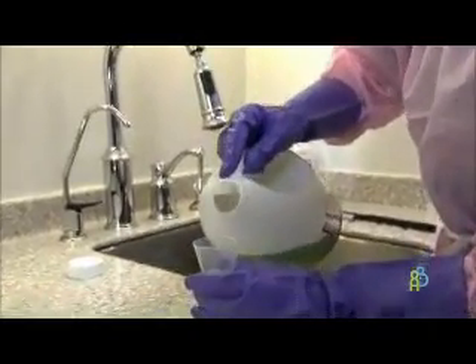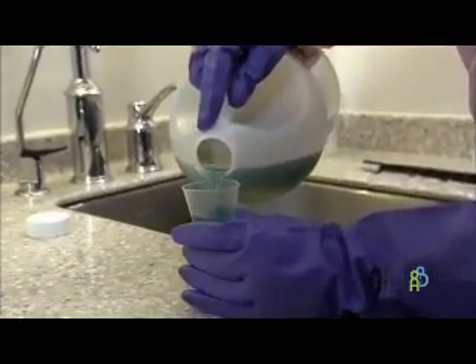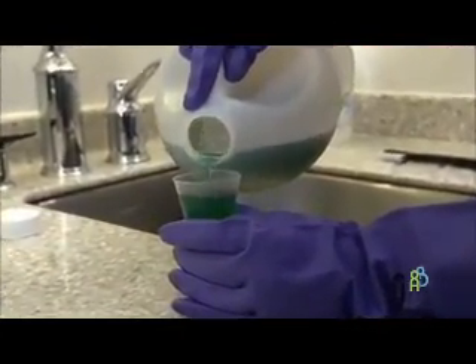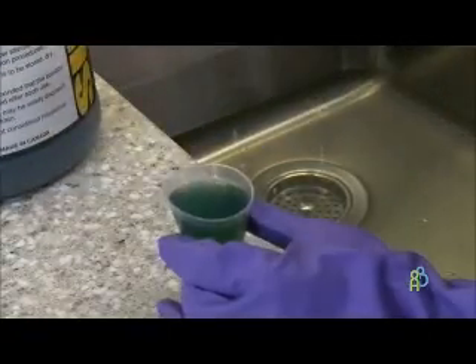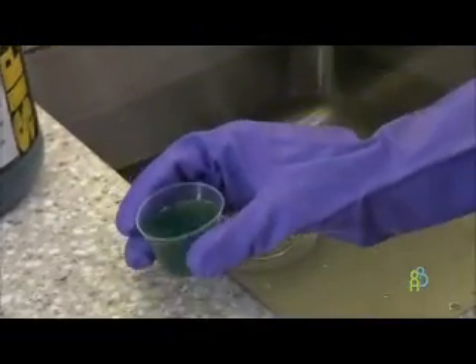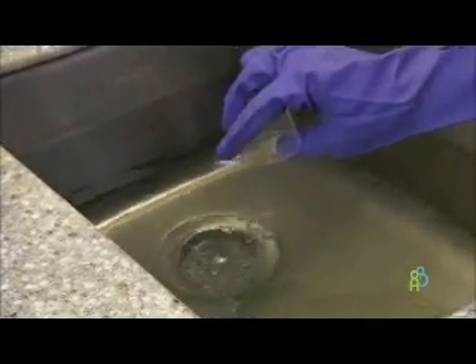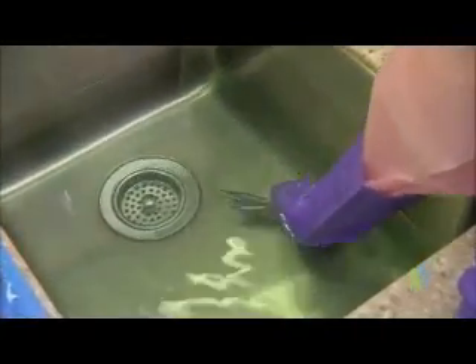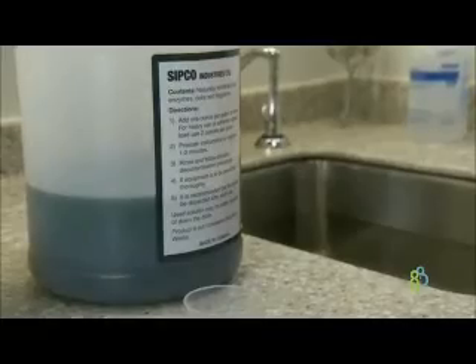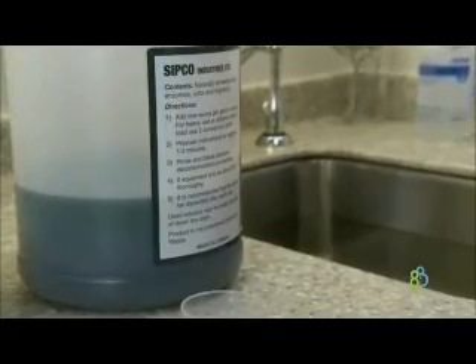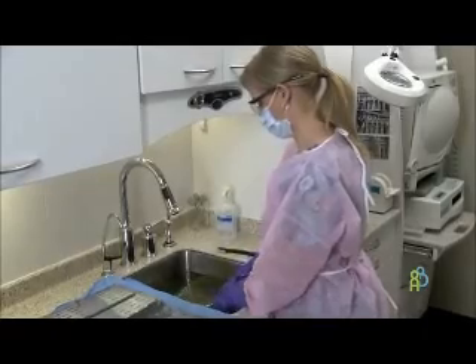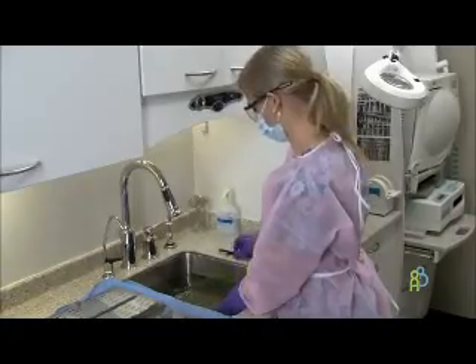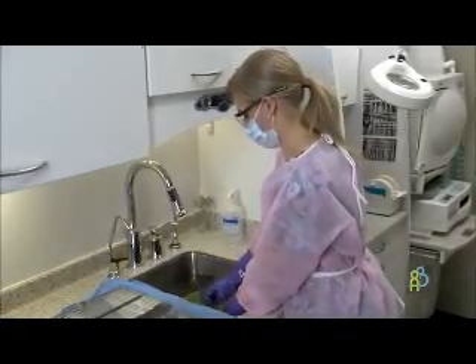When manually cleaning devices in a sink, it's important to minimize the generation of splashes and aerosols. It's also important to follow the instrument detergent or enzymatic cleaning product manufacturer's instructions for dilution and use. These are usually written on the label or on the accompanying product monograph. This means that cleaning should be done under the surface of the water using a long-handled brush and low sudsing and free rinsing instrument detergent or enzymatic cleaner rather than under running water.